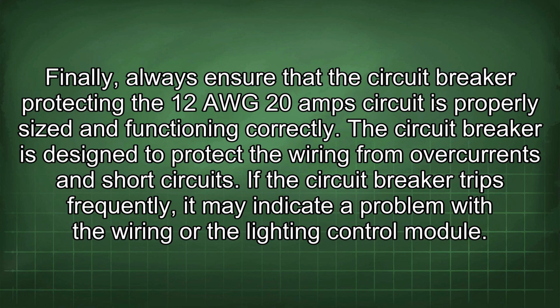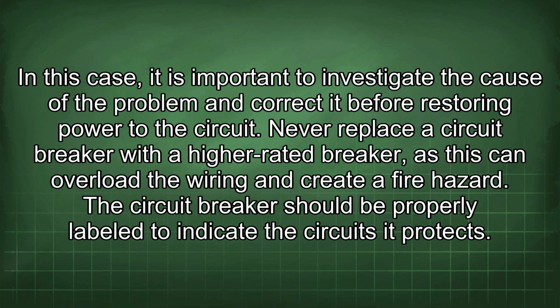Finally, always ensure that the circuit breaker protecting the 12 AWG 20A circuit is properly sized and functioning correctly. The circuit breaker is designed to protect the wiring from overcurrents and short circuits. If the circuit breaker trips frequently, it may indicate a problem with the wiring or the lighting control module. In this case, it is important to investigate the cause of the problem and correct it before restoring power to the circuit.